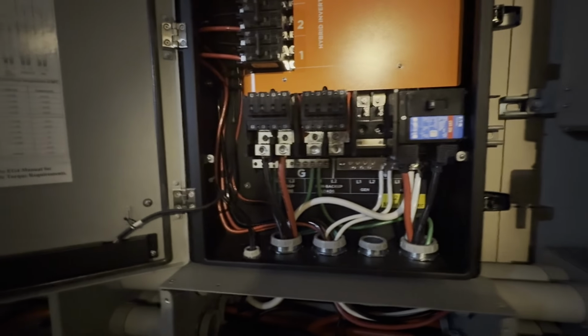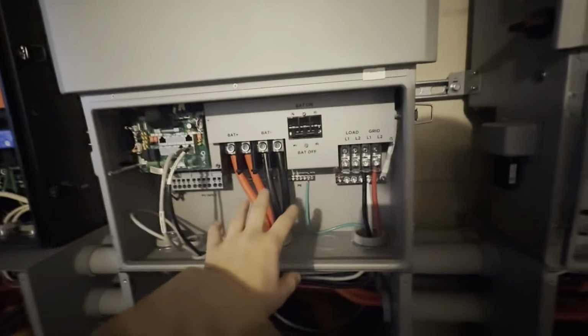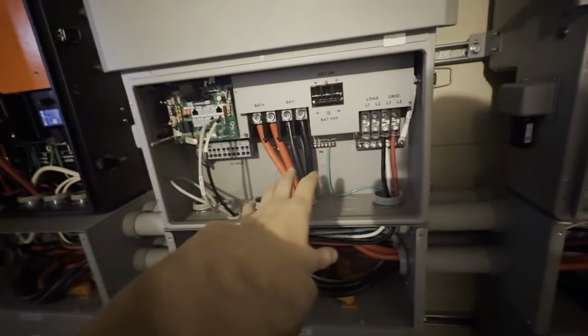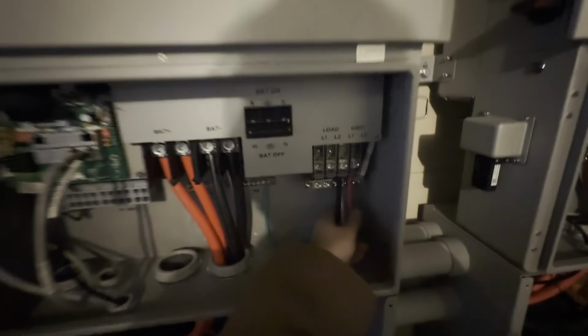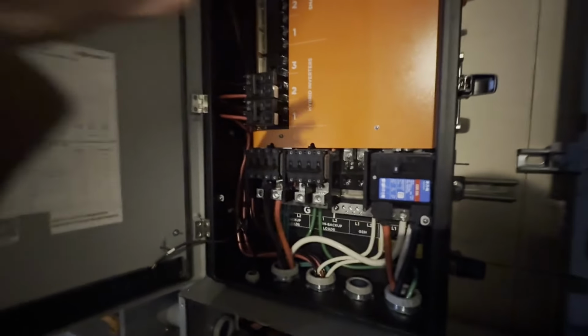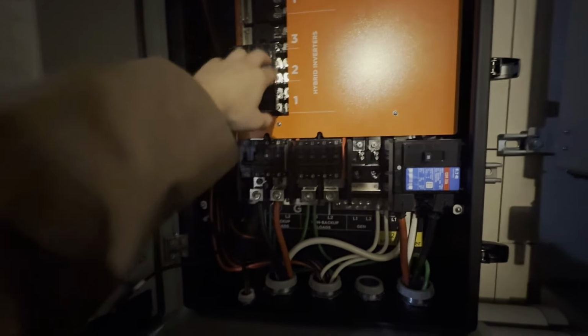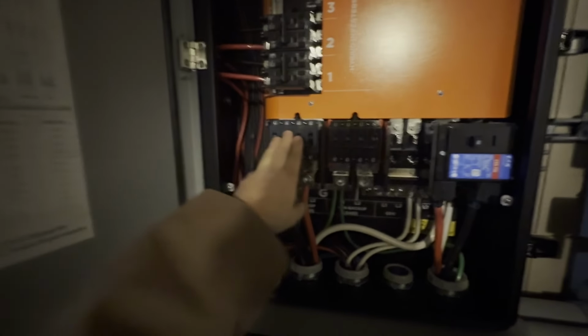So we've got the main panel, the microgrid interconnect device, the brains of the system, and then the inverters. The inverters are connected to the batteries. They take the 48 volt DC from the batteries and convert it to 240 volts AC, which is what these lines are, and send it to the mid, which then determines based on conditions whether to draw from the inverters and send it to the house, or draw from the grid and send it to the house.